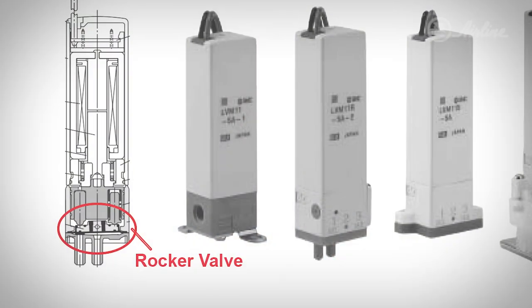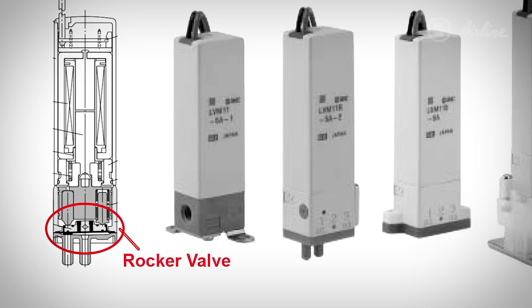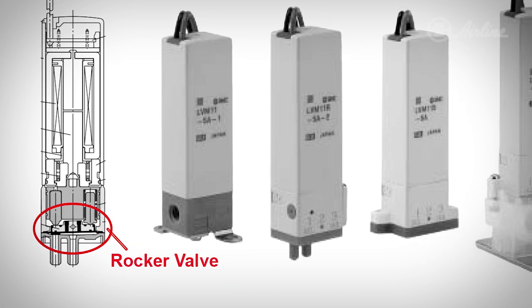Rocker valves have a compact size, are usually a lot smaller than diaphragm valves, and have a low internal volume with fast actuation times. On the other hand, rocker valves are not as well swept as diaphragm valves, so they typically carry more dead volume — meaning media can remain within the valve after use. Rocker valves also cannot sustain corrosive chemicals, which gives them a shorter lifespan. In those cases, you could turn to diaphragm valves.